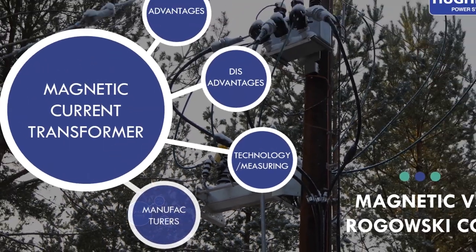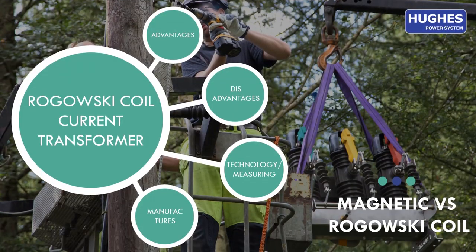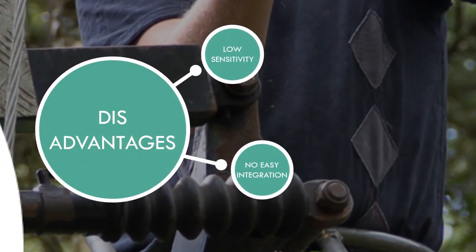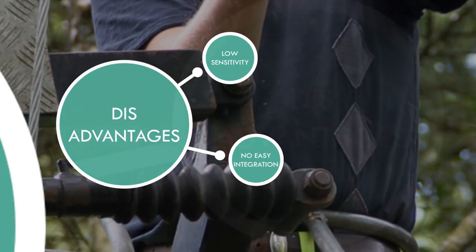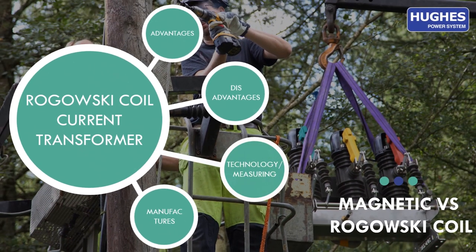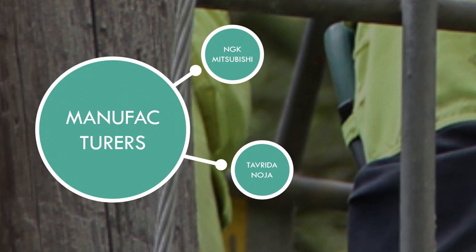Now we will have a look at the parameters of Rogowski coil current transformer. The strong sides are that it is linear over a wide range and it is cheap. The weak sides are that it has low sensitivity because it measures 1,000 ampere in millivolt and it has poor compatibility with different types of protection relay. The technology behind Rogowski coil is an air-winded coil without a magnetic core and measuring is thousands of ampere in millivolt. The manufacturers that produce reclosers with Rogowski coil are NGK, Mitsubishi, Noja Power, and Tavrida.